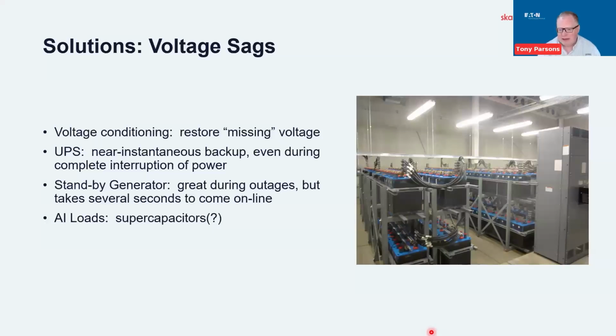It just gives you an idea of the amount of energy storage that may be needed. But the idea being that if the utility power goes out of spec, then let's bring in some of that stored energy to help make up the difference. Of course, that only gets you so far. And so if you're looking at potential extended outages, you may have to go to standby generation, right? Great during outages, but what do you do in the several seconds that it takes for that to come online?